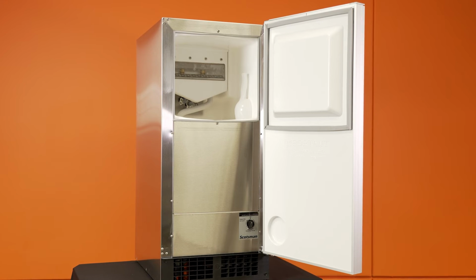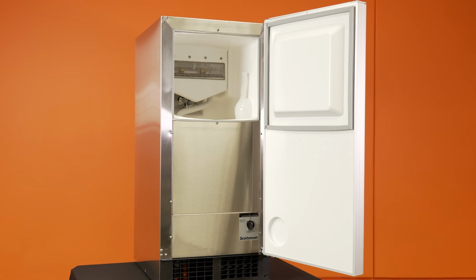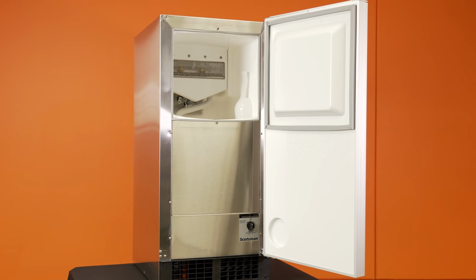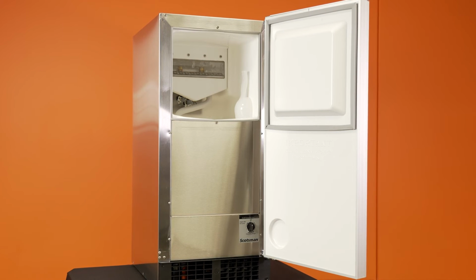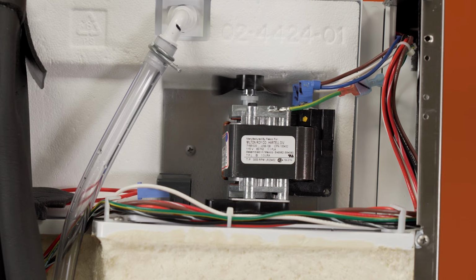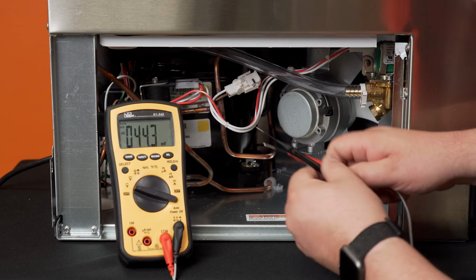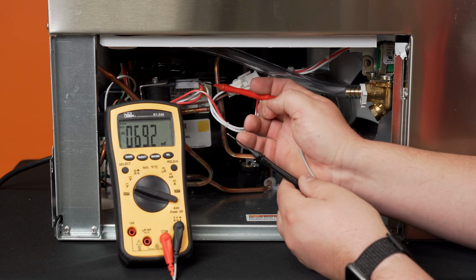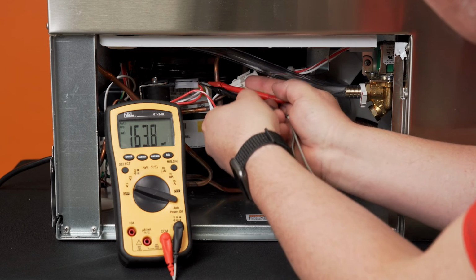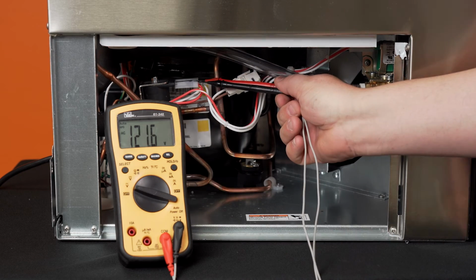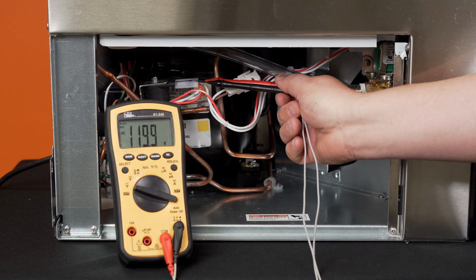If ice is not forming on the evaporator plate during freeze, the following tests should be performed to confirm the operation of the hot gas valve. Confirm the unit is in freeze by noting when both the spray pump and condenser fan are running. During freeze, the hot gas valve should not be energized. If power is found at the valve, replace the control board.